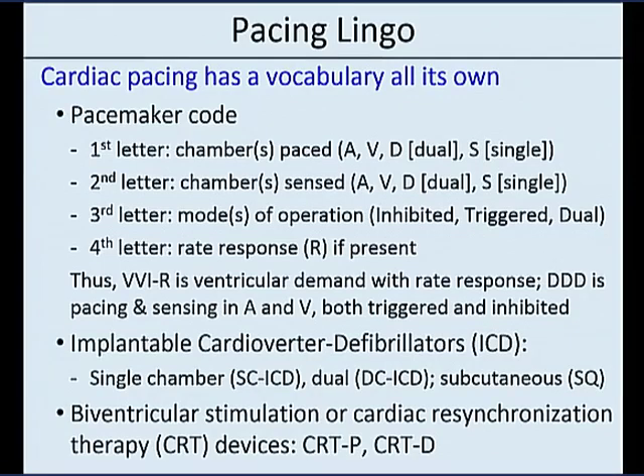And the fourth letter is a rate response, if present. There's a fifth letter out there as well for tachy response. We don't ever use that. So for instance, a VVIR pacemaker is a ventricular pacing, ventricular sensing, and inhibited by a spontaneous ventricular event, and it paces more rapidly in response to perceived physiologic need. A DDD pacemaker paces and senses in both atrium and ventricle, and is both triggered and inhibited.